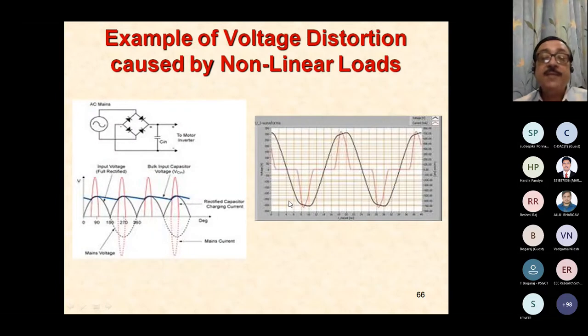So this is a typical example of voltage distortion by a diode rectifier load. So you can see the voltage is clipped at the top. It's a distorted voltage waveform because the diode rectifier does not draw any current for this duration, neither does it draw for this duration, but for the middle part of the half cycle, there is a huge draw of current. The current achieves a large peak.